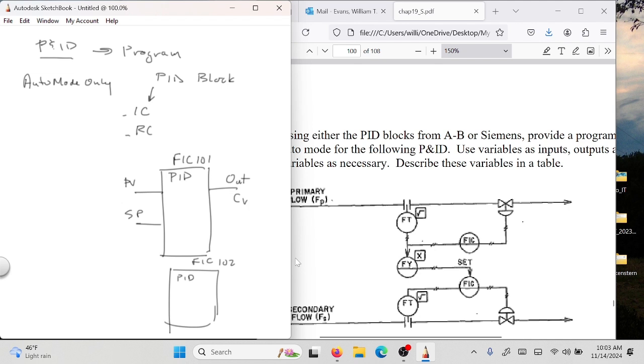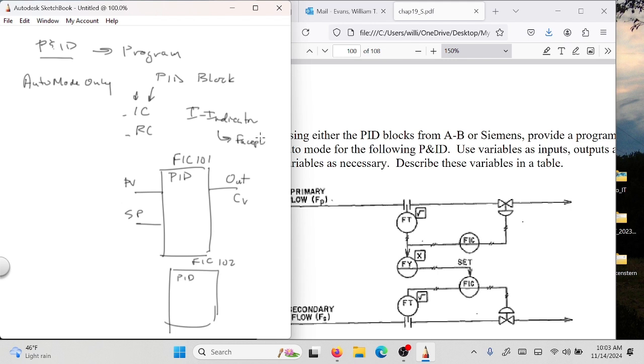What does FIC stand for? Flow Indicator Controller. The I stands for indicator, which means a faceplate — something that an operator can come up and look at and change. Remember from chapter 15, those physical bars the operator would be looking at? Those would be a PID controller that you click on to go into auto or manual. We're talking about auto only right now, but you can take that PID controller to manual if you want to.